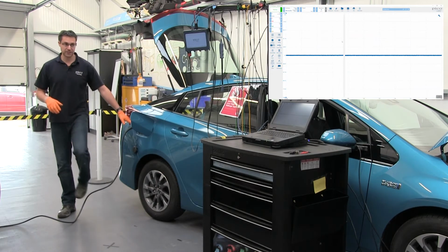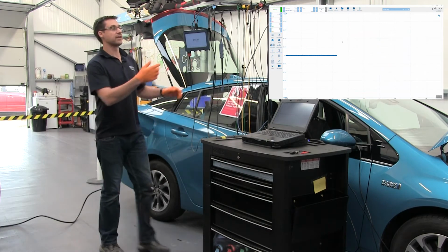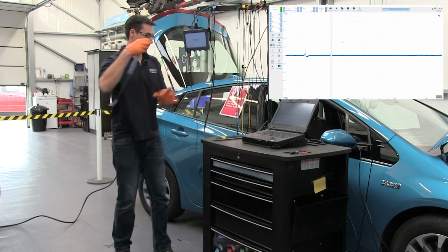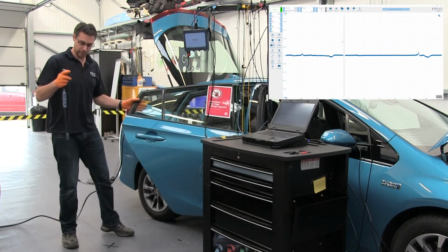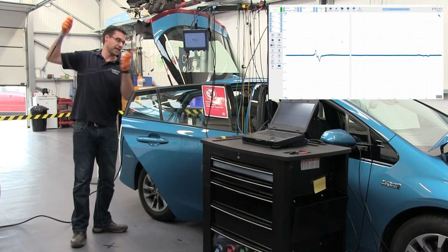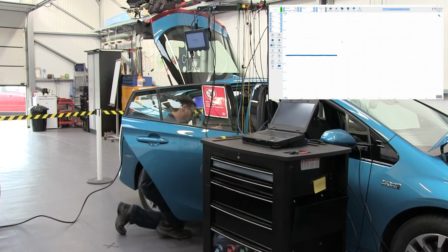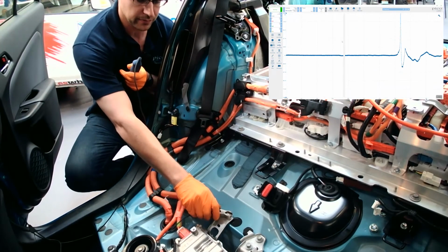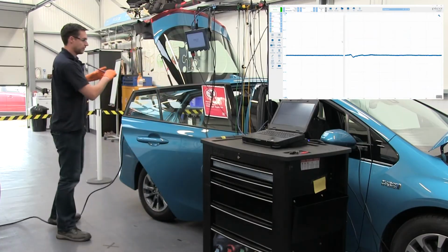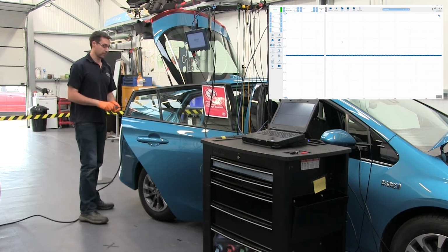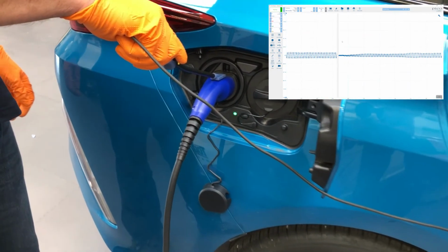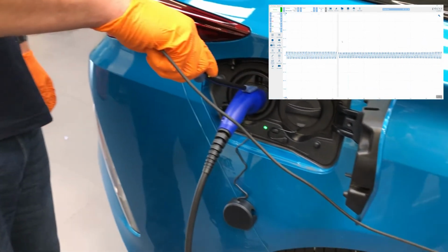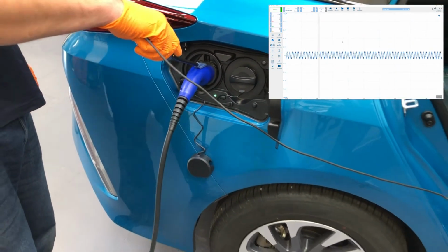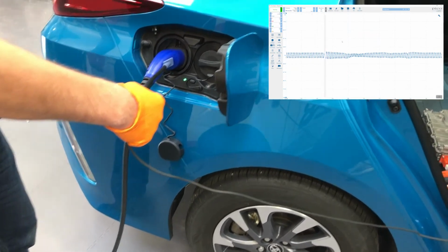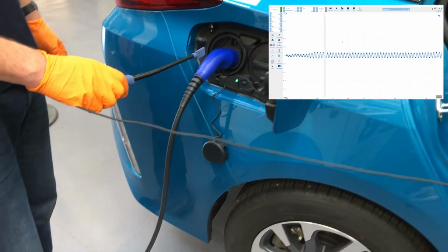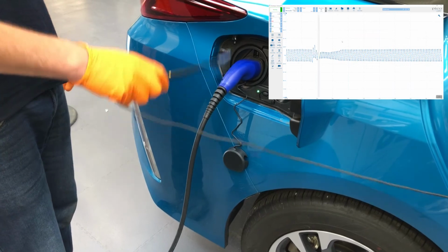So we can assume that if this is working, then we should have electrical activity around it. So what we'll do is we'll take our coil-on-plug probe, and we'll connect it to a chassis ground using the grounding clip. And the first thing we're going to do is just offer the coil-on-plug probe up to the housing on the Type 2 connector. So you can see there we've actually got activity present, and we can see how that intensity changes depending on the location of the coil-on-plug probe.